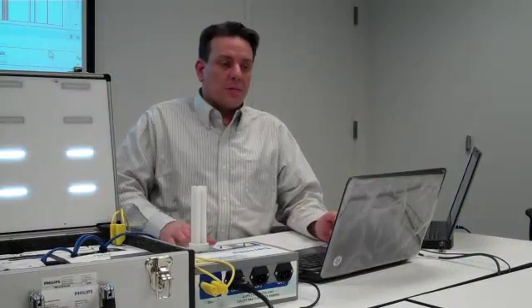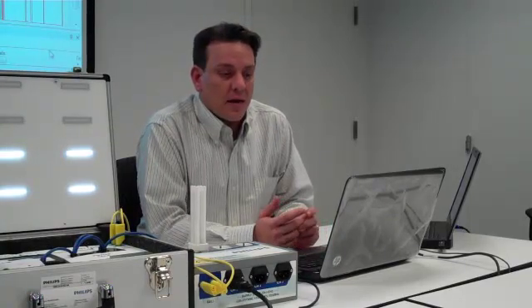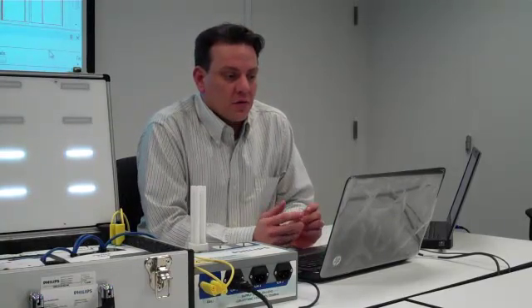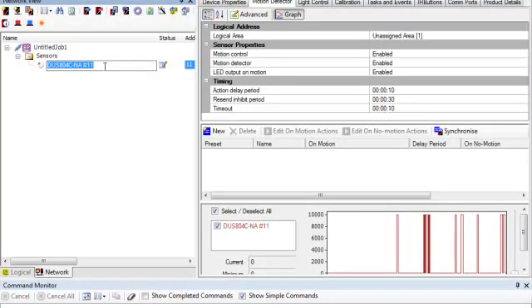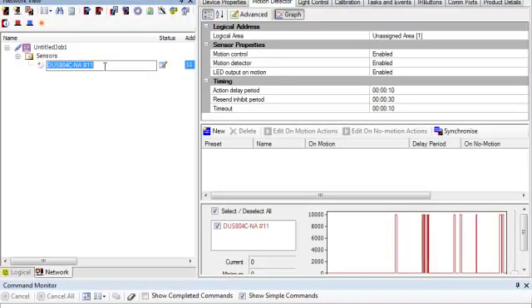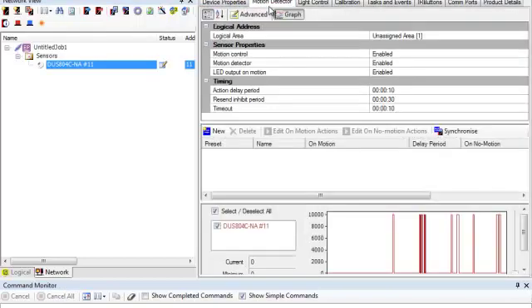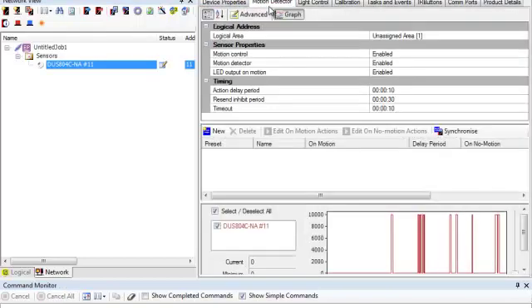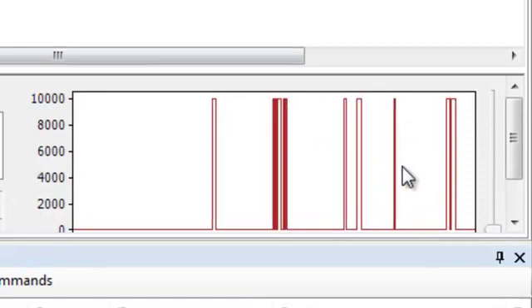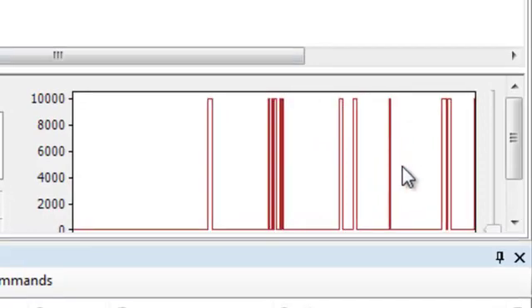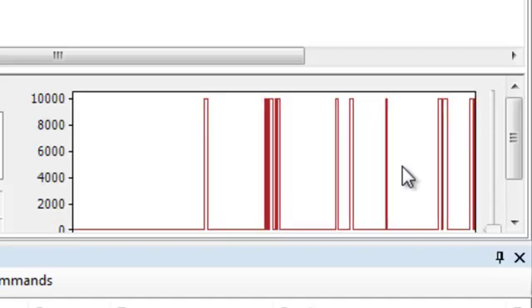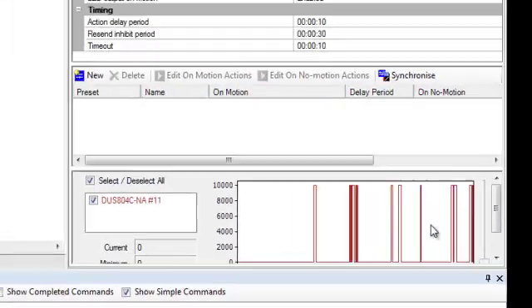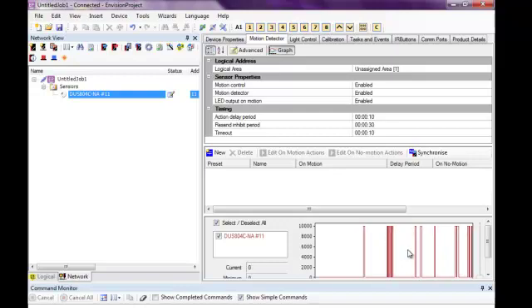Quickly we're going to talk about programming occupancy sensors or vacancy sensors. Essentially all our sensors have a photo sensor as well as motion and light control. So what we're going to look at here is some of the more advanced features. Here you see I have a sensor in my project, and I'm going to go ahead and look at the device properties of it, and now the motion detector properties. So here I can see what the actual motion detector is seeing at the time. So if I need to adjust this for an open door or for a blank space that is seeing outside of the area that I'm actually trying to control, I can adjust that because I can see this live level as it's happening.